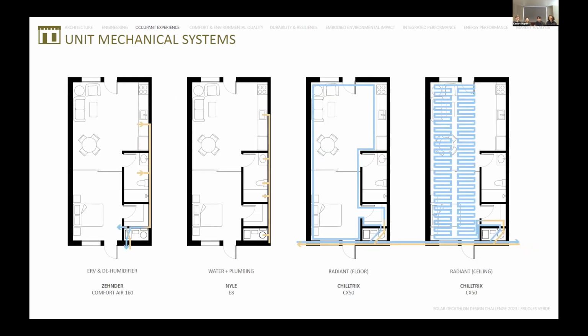In each unit, the ERV pulls in hot, dry exterior air and transfers some cool, moist air. There is a separate dehumidifier in each unit that will only be needed during the 2 months of monsoon season to prevent condensation when the dew point is higher than the 60 degrees of our radiant cooling system.